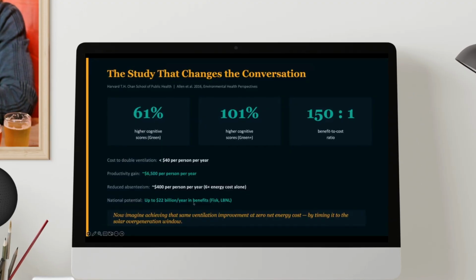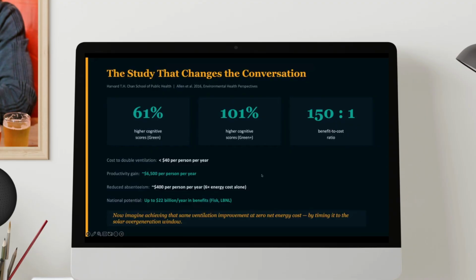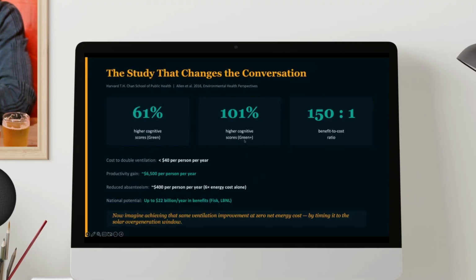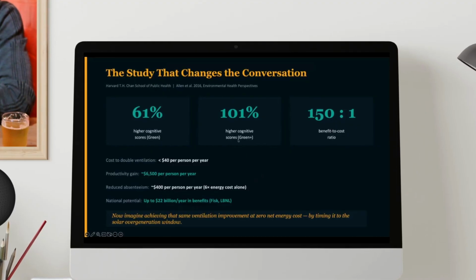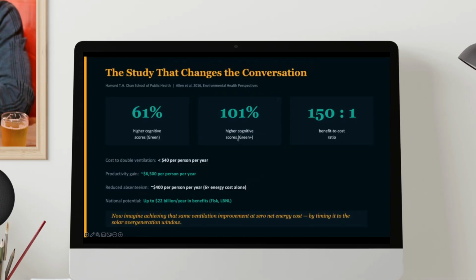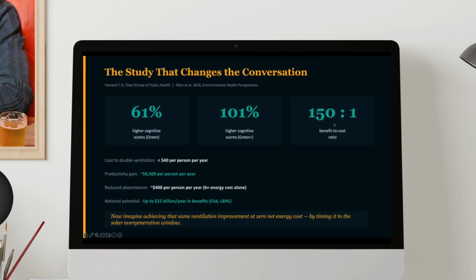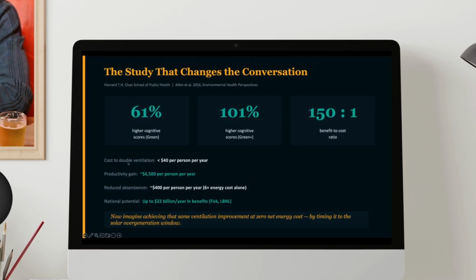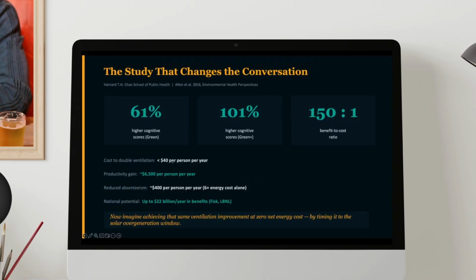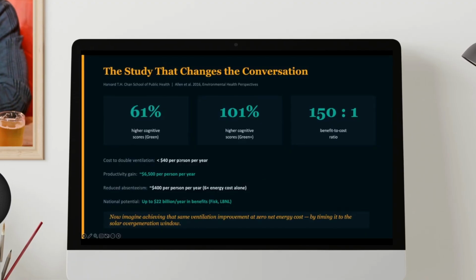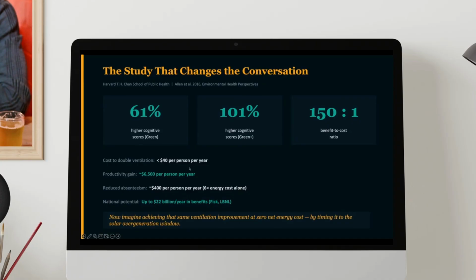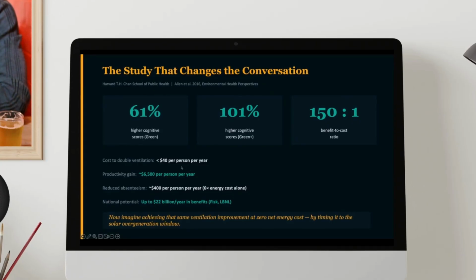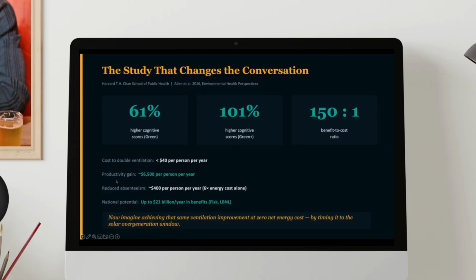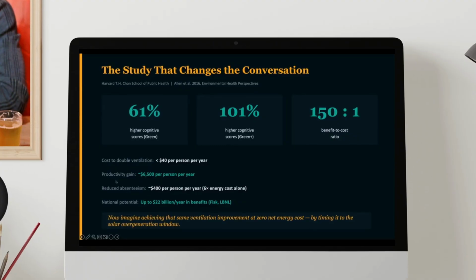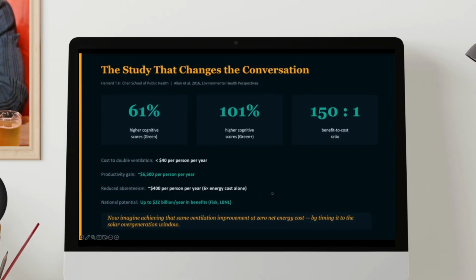I think they had several dozen people that they did this with over the course of like 9 weeks or something. But you can see that higher cognitive scores in the best buildings were double what they were for other buildings. So that's pretty remarkable. And the cost benefit ratio. So what they were saying is that to double the ventilation, which is roughly what green plus means, would cost about $40 per person per year for occupants of the building, versus what the productivity gain should be of around $6,500 per person per year.